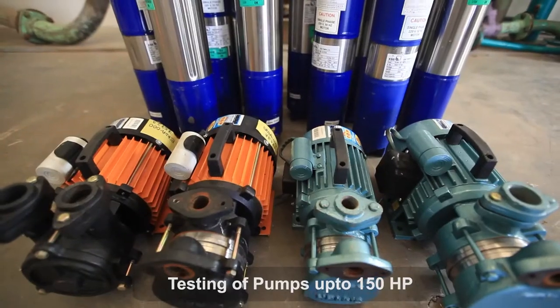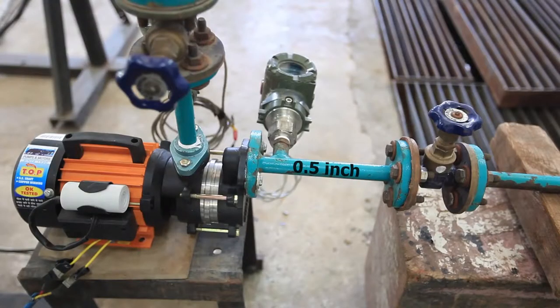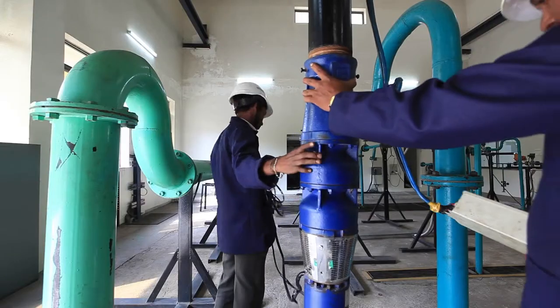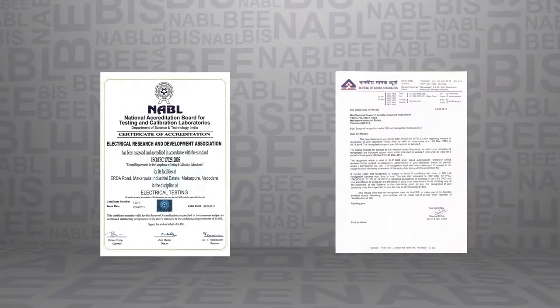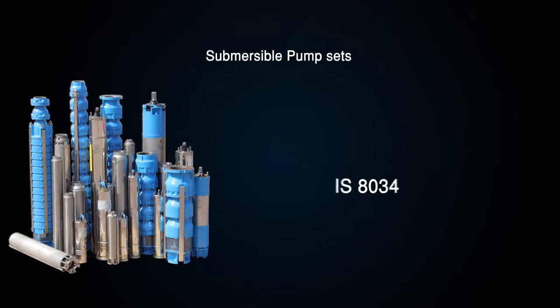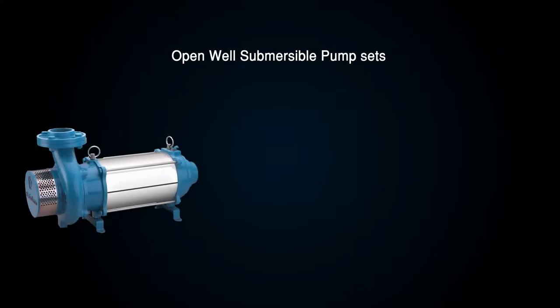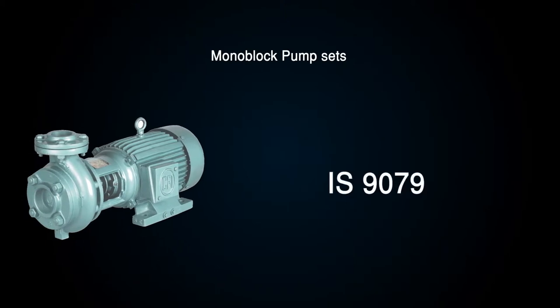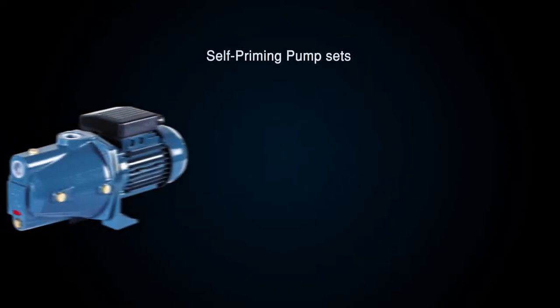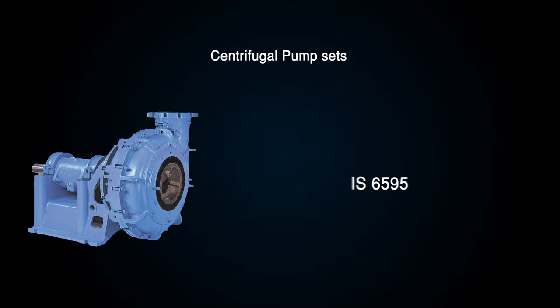The pump test facility undertakes testing and evaluation of pump sets up to 150 HP, with 0.5 to 8 inch delivery pipe sizes at 50 and 60 Hertz. This facility is recognized by NABL and BIS for testing of submersible pump sets as per IS 8034, submersible motors as per IS 9283, open well submersible pump sets as per IS 14220, monoblock pump sets as per IS 9079, self-priming pump sets as per IS 8472, and centrifugal pumps as per IS 6595.